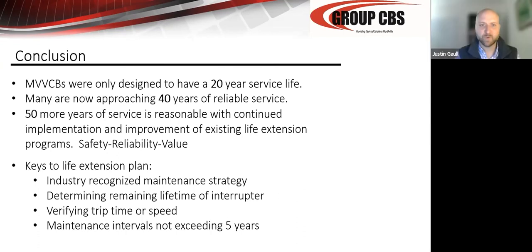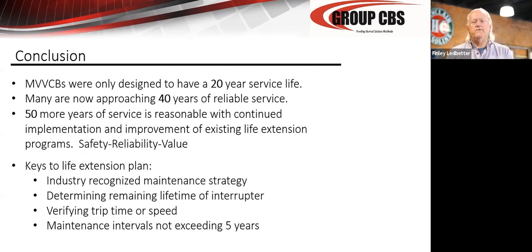Great. Let me see if we got one more coming in. What's the model of circuit breaker timer that you would recommend? Everybody makes a timer. Some of them are very expensive, and they typically have the ability to feed travel, distance and velocity information into the result. If you're looking just to do a parting test, which is the minimum I would recommend, there are lots of them out there that'll do it.